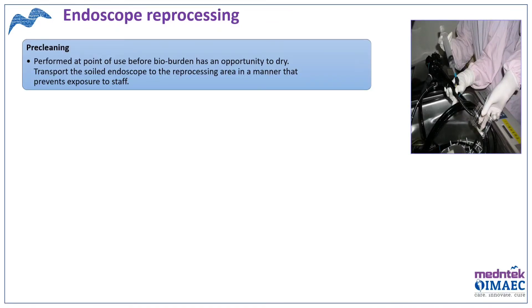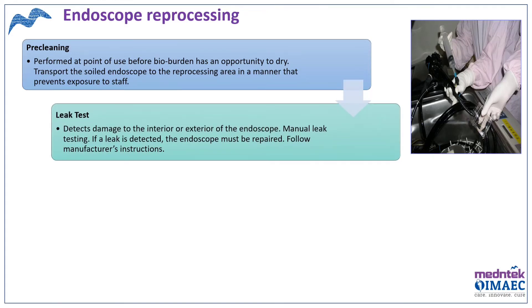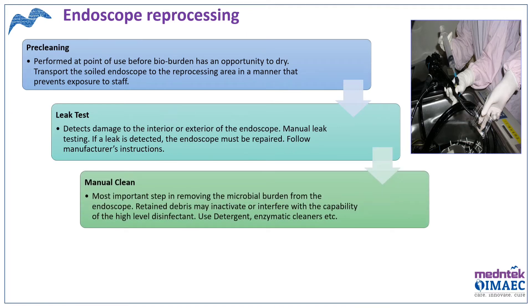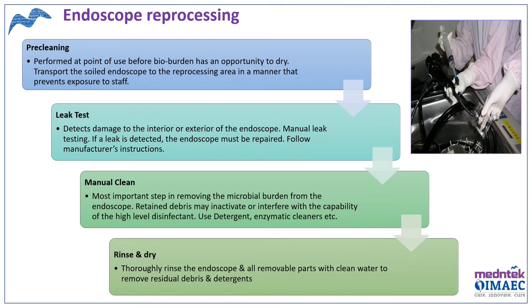After pre-cleaning, instruments are taken for disinfection. As an example, we will look at endoscope reprocessing. The first step is pre-cleaning, where the bio-burden and organic material or soil from the endoscope is reduced. Next is the leak test, where the endoscope is tested for any leakages to ensure proper functioning. Then comes manual cleaning, where the endoscope is dismantled and every part is manually cleaned with detergent or enzymatic cleaners. After that, the endoscope is rinsed and dried to remove detergent or residual debris.